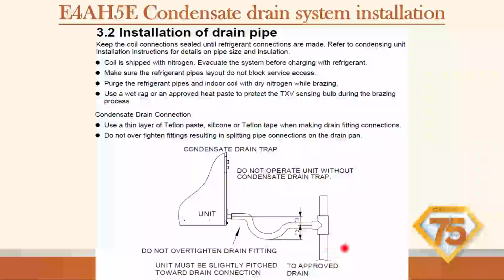And then please, and this goes for gas furnaces too, we need that atmospheric T, because once it hits it, if we don't have an atmospheric T and this is just a 90, it's possible that it won't drain right there and it'll create a suction. So if it's got the breather T in there, it will allow that to drain. That could be going straight into the bottom of a condensate pump and not be able to drain that way too. So the atmospheric T eliminates any kind of worries about it.